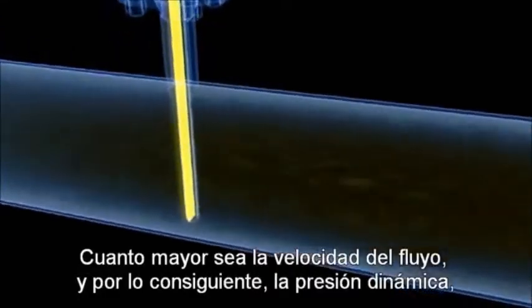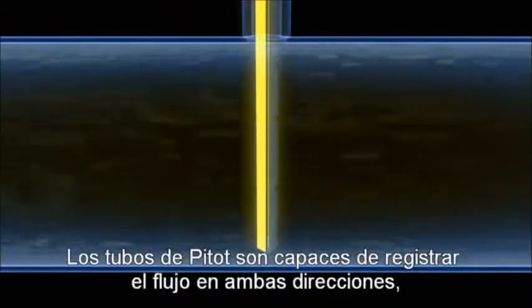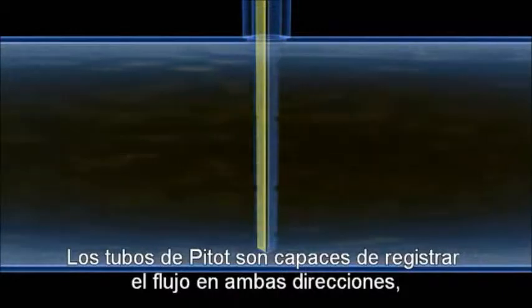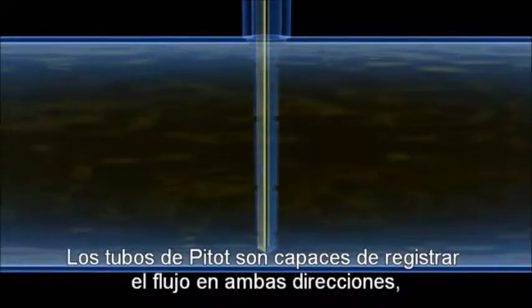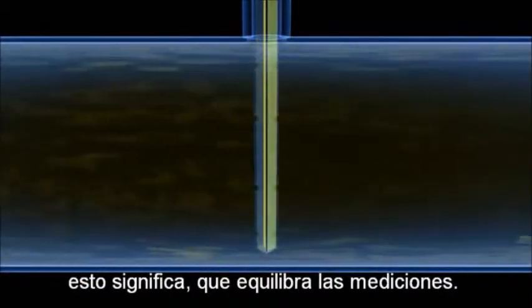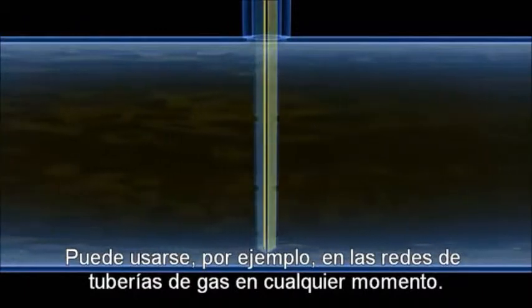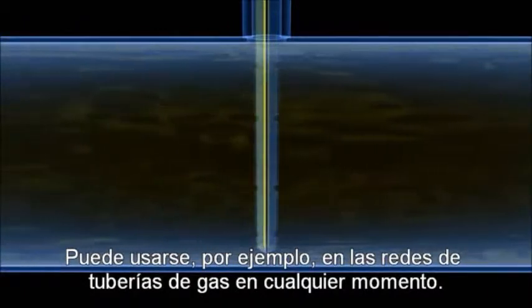The higher the flow velocity and therefore the dynamic pressure, the greater the differential pressure measured. Pitot tubes are able to register the flow in both flow directions. This means that balancing measurements, for example in gas pipeline networks, can be carried out at any time.